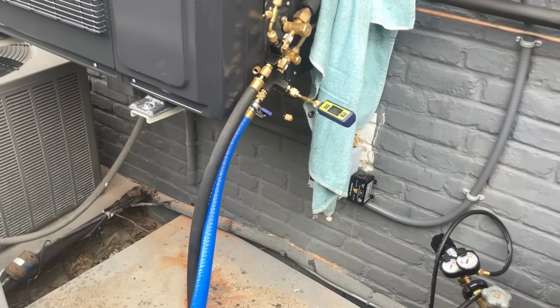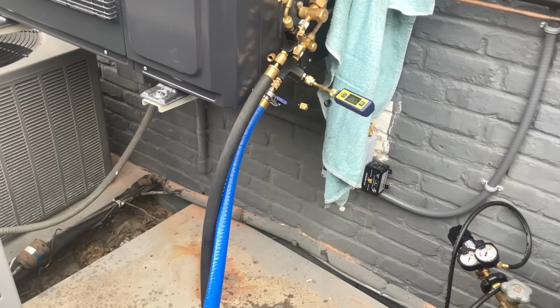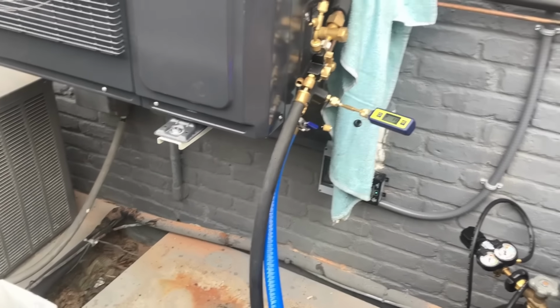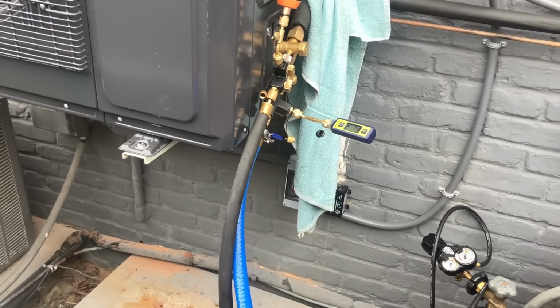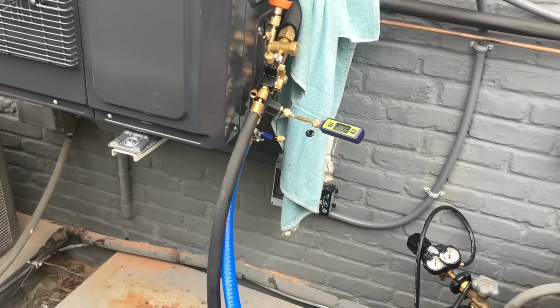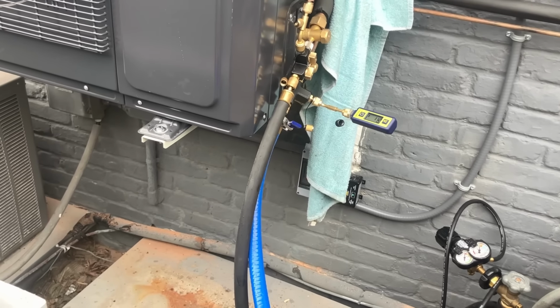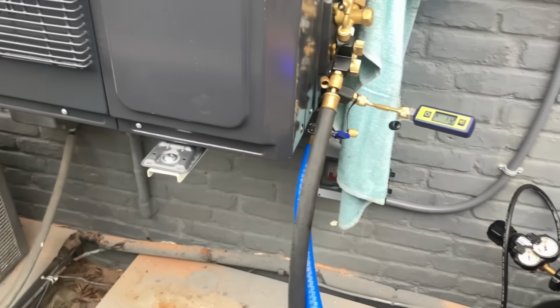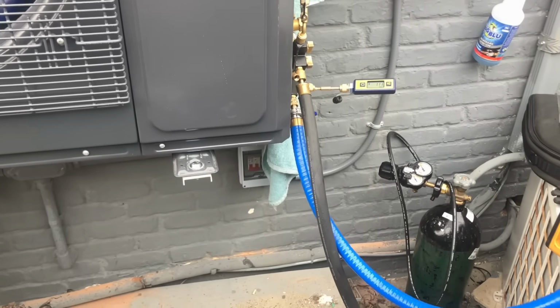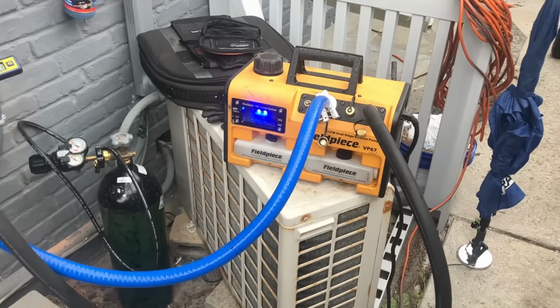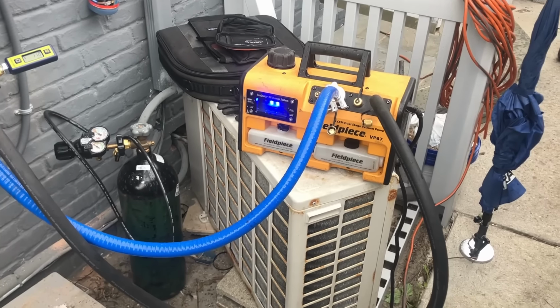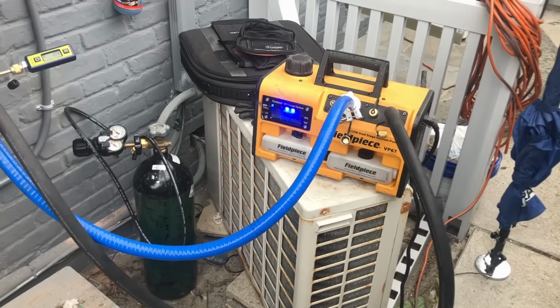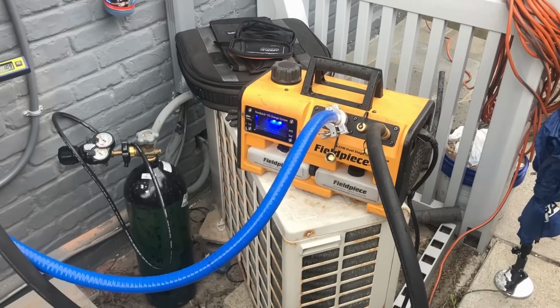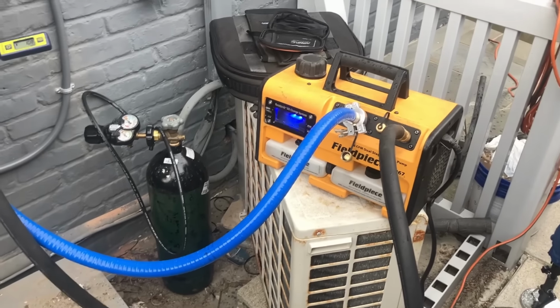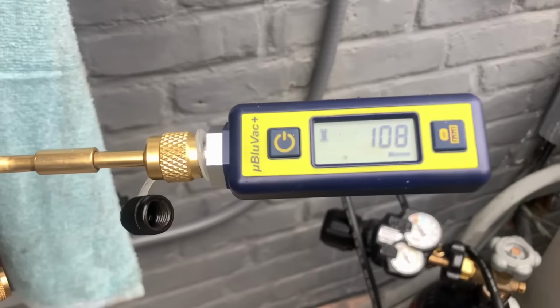Maybe there's a leak. Maybe there's more trapped moisture that's still boiling off. Either way, we're not going to accelerate this stage of the installation process. The commissioning process is the most important part, right? Because we don't want to introduce any refrigerant until we know that the system is clean, dry, and tight. Listen, folks, a proper vacuum isn't just something that your customer can see, right? It doesn't show off with fancy photos, unless you're like an influencer like me, right? Showing off how deep we are at 108 microns, right?